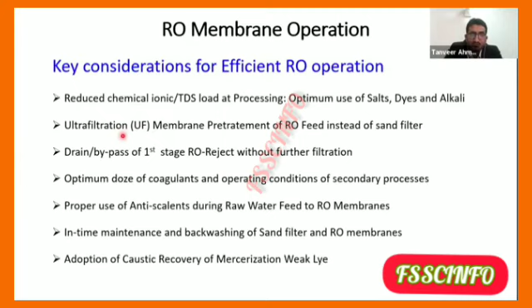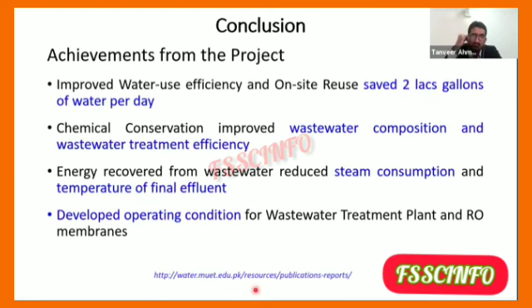And with these achievements and targets and the development of the water management system, we were able to save around 2 lakh gallons of water per day. And we also stabilized the wastewater treatment plant operation. We also recovered some energy in the form of steam condensate recovery and use of heat exchangers. We also developed 4 scenarios and different conditions for running a wastewater treatment plant more effectively, because in the textile industry, due to a lot of process variation, it is very difficult to manage the wastewater treatment plant operation. So we designed conditions related to changes in the process, to tune the wastewater treatment plant accordingly. I have shared here the link to access this project report if you are interested.